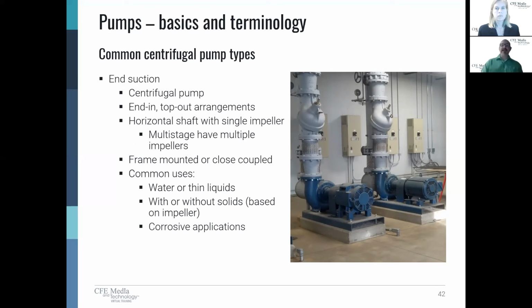But engineers have to communicate. If I'm going to do vibration isolation, we can see we have vibration isolation in the piping itself. It's that braided section right above the pump. And I also have something on the base as well. All of that takes up physical space, and it affects the serviceability. So we want engineers to think about these things, and we want them to coordinate.